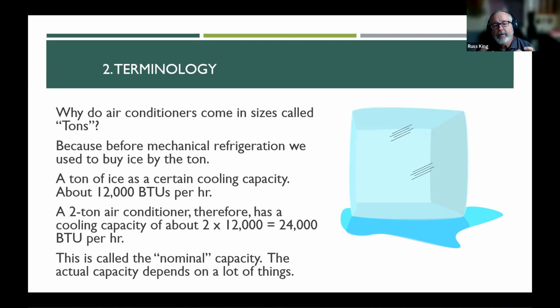But we call that the nominal capacity. That's what we call that unit. We're going to call that unit a 4-ton. We're going to call that unit a 5-ton. It has nothing to do with the weight, okay? They're much lighter than that. They represent a ton of ice.